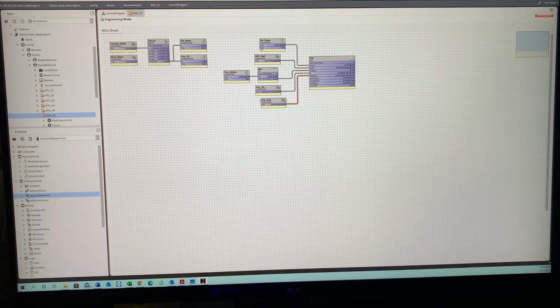So here we go. We have a basic PID set point where we have our discharge air temp sensor, our discharge air set point, and our fan status, which will enable. So that's why it says disable: if it went true, it's going to disable the PID. You have your cooling throttling range, your cooling integral, and then here's our output. Now with Honeywell, this output will go -200 to +200.